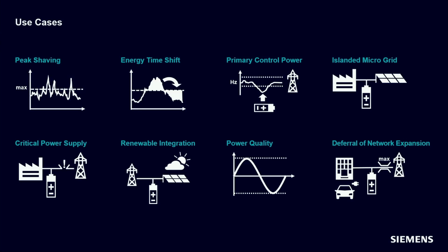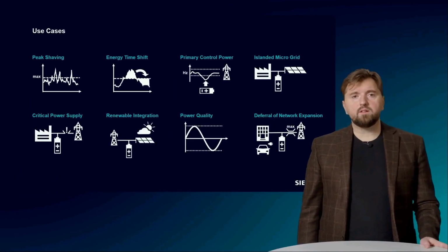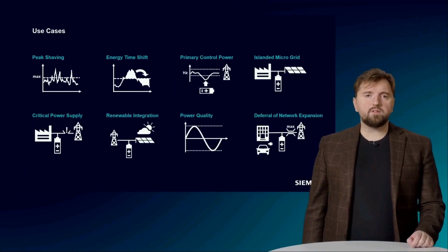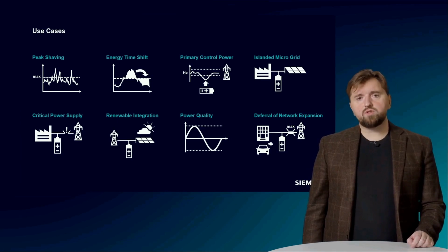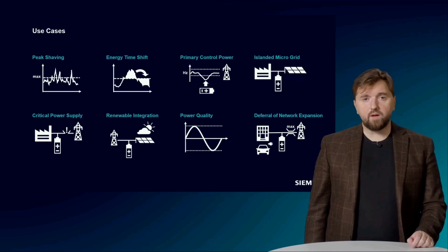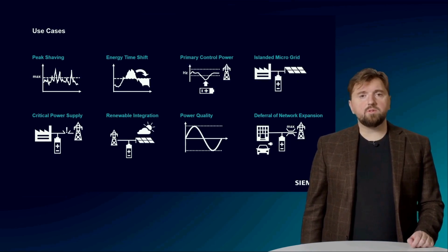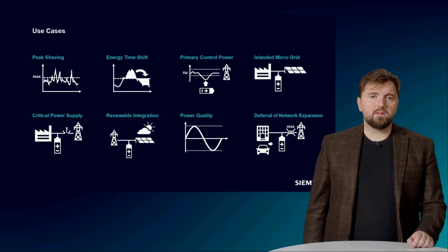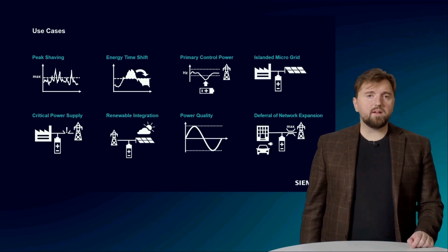A crucial function of BESS is frequency regulation and grid balancing. And here it's all about maintaining continuous balance between power generation and load, compensating for the fluctuations. For resilience, BESS is key. It can keep an islanded grid, like a microgrid, powered even if the main grid goes down. Here especially a grid-forming capability of BESS becomes important. During outages, BESS proves invaluable by supporting critical loads, thus ensuring continuity and providing much-needed backup.